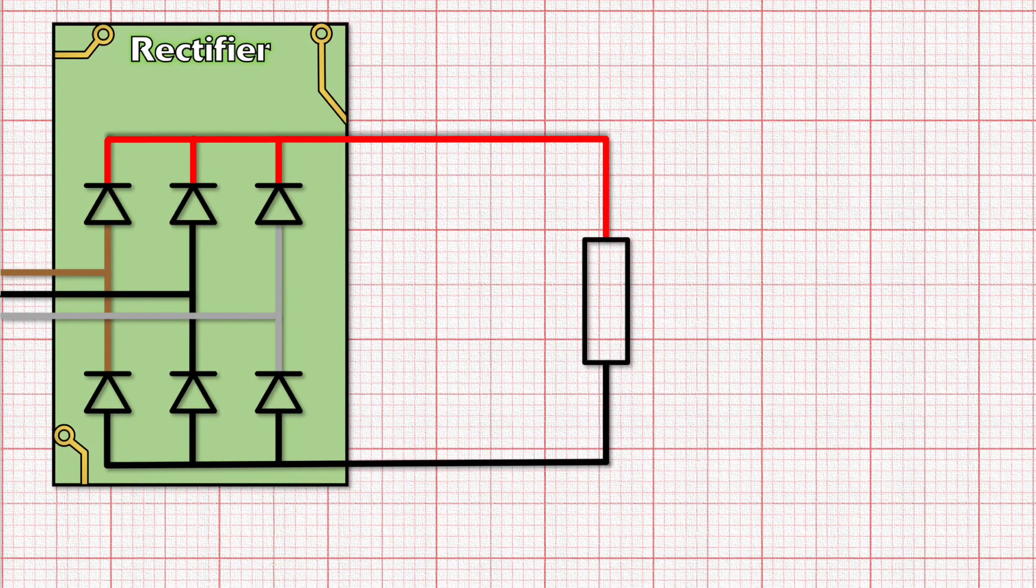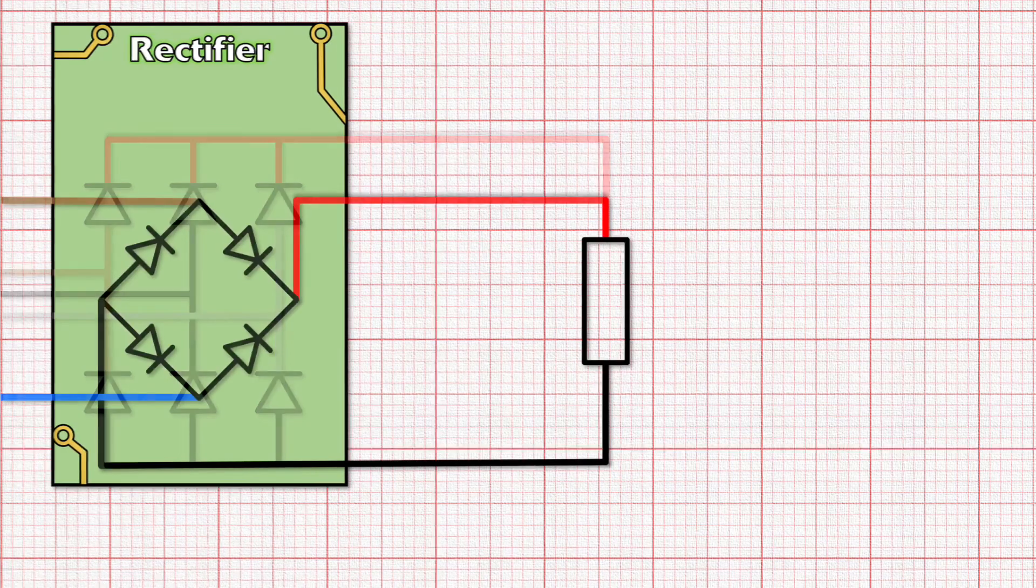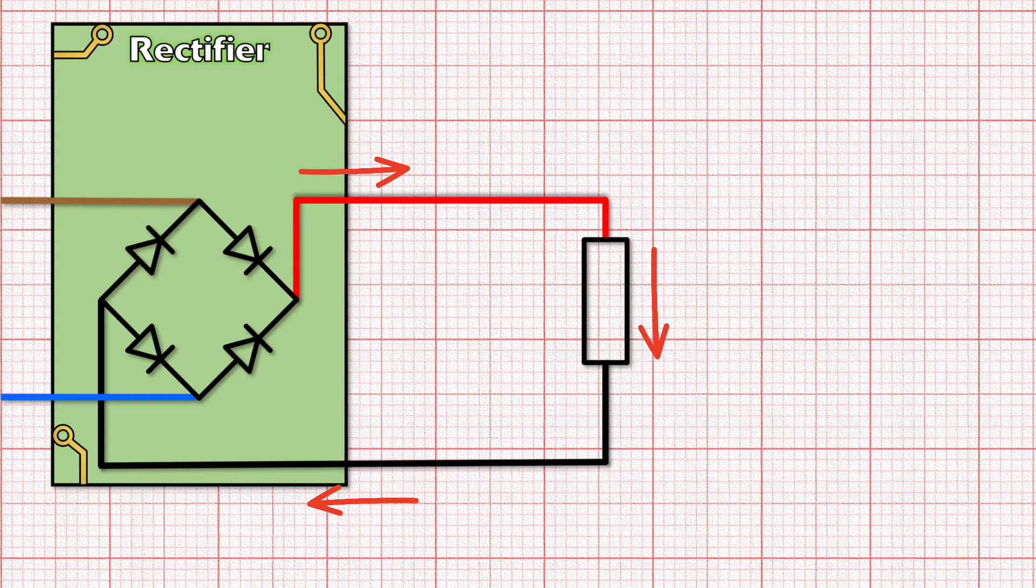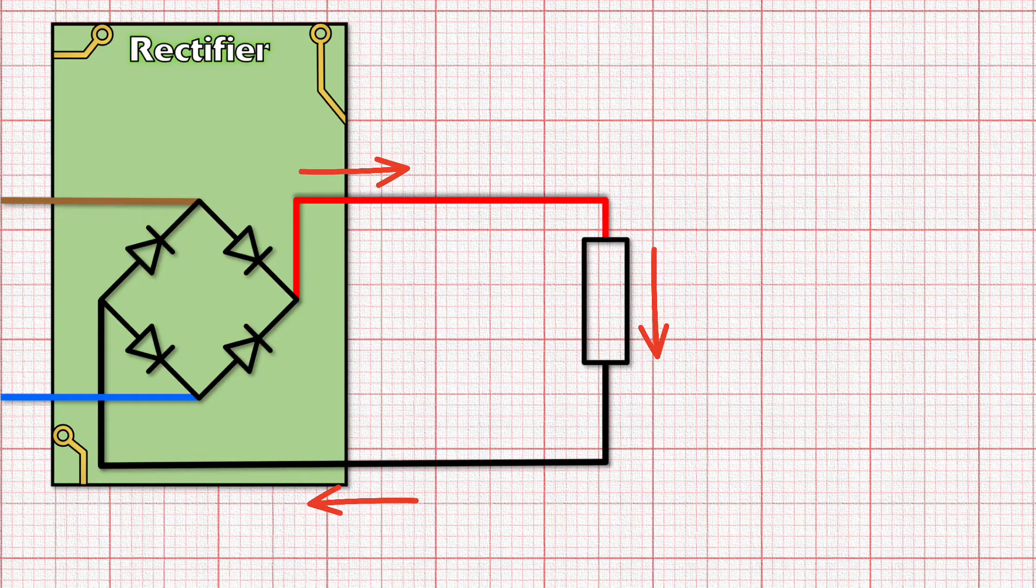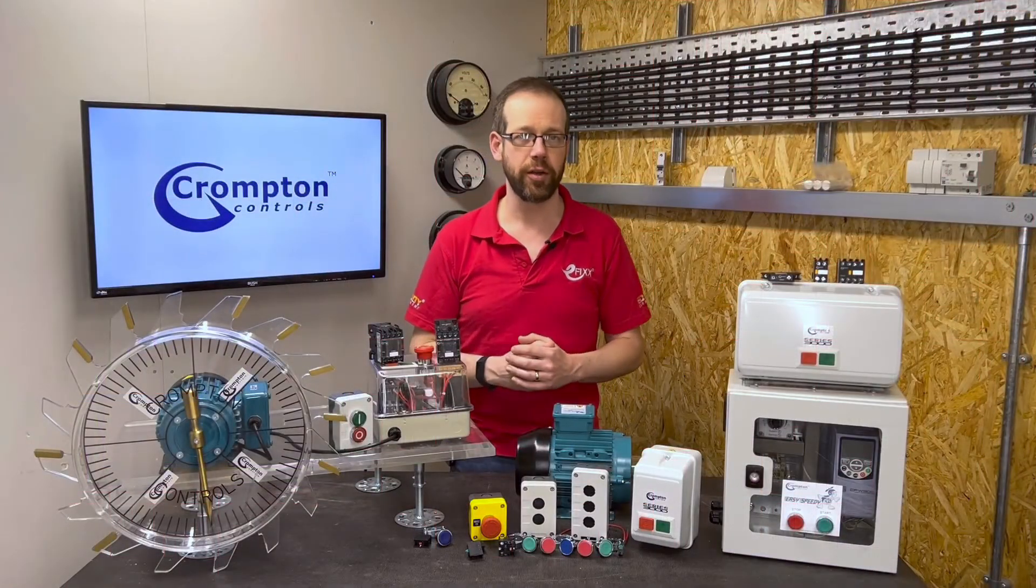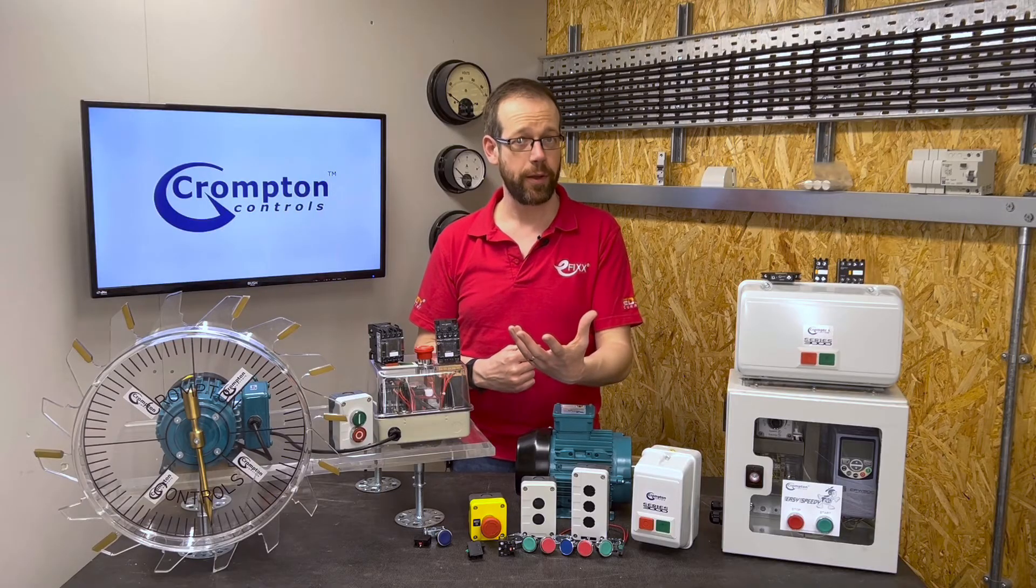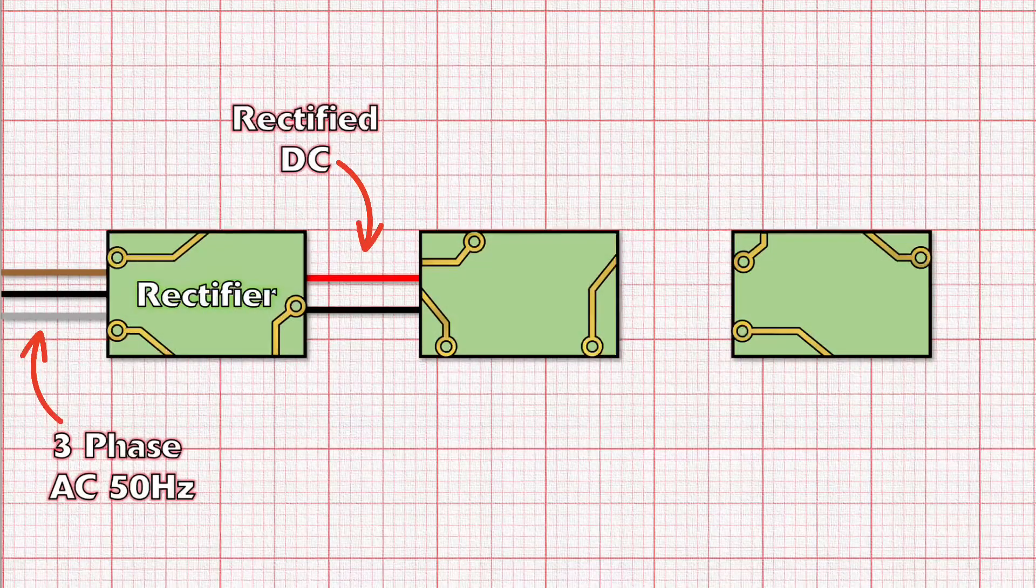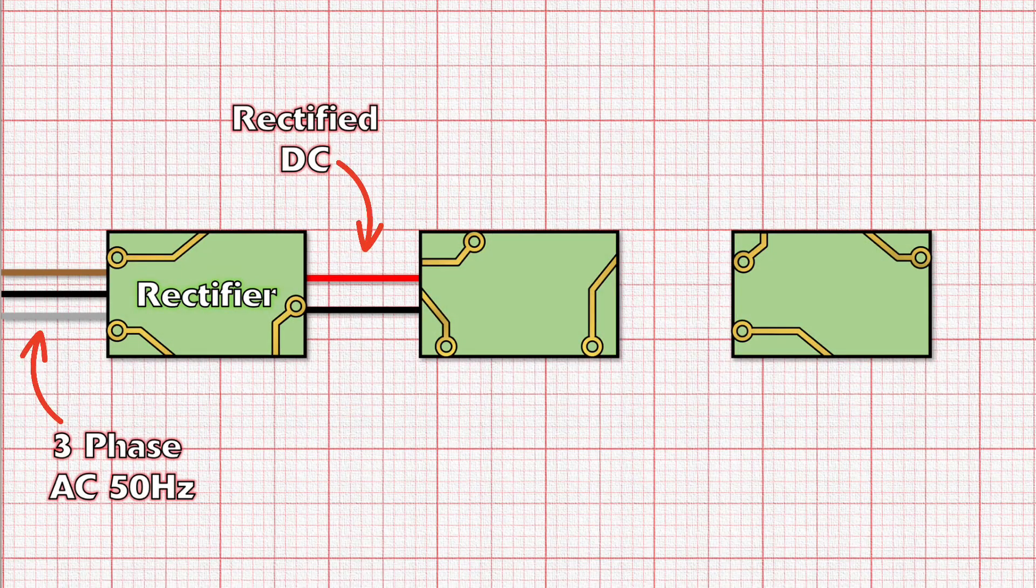Now one really clever thing about changing the supply to DC is that it means we can also use similar principles to convert a single phase AC supply to DC as well. This only requires the use of four diodes arranged in a slightly different way. But from this point on, everything that happens to the DC current will work as well for a single phase source as it does for a three-phase source. So as we'll see, what that means is that we can use the principles of a variable frequency drive to create a three-phase supply from a single phase supply. Clever.